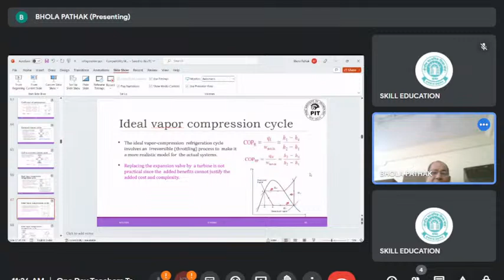For the COP of the heat pump, it is QH upon W_in. QH is what we are supplying to the hot body, that is H2 minus H3, the heat rejected in the condenser that is supplied to the hot body. So for the heat pump, COP is H2 minus H3 divided by H2 minus H1. This is the working of the ideal vapor compression cycle COP relations.